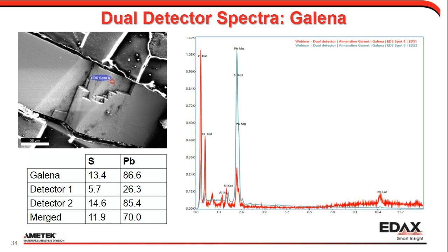And if I look at the spectra from the two detectors, I can see detector 1, there's a big problem here. If you look at the high energy range, you can see I have a hump in the high energy range and it drops down in the low energy range. And that is not normal behavior if you have a flat sample. Obviously, this is not a flat sample, but what's going on here is that you have additional absorption. So high energy X-rays can escape through more material quite easily, whereas the low energy X-rays will be attenuated. So we have a lot of attenuation going on here.